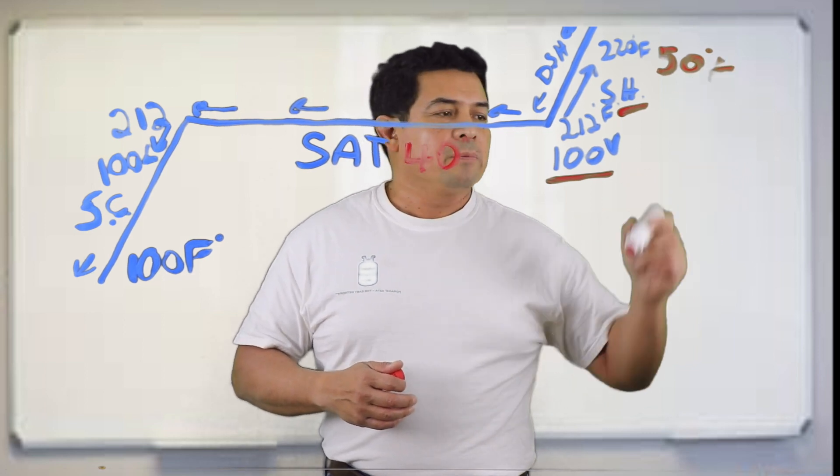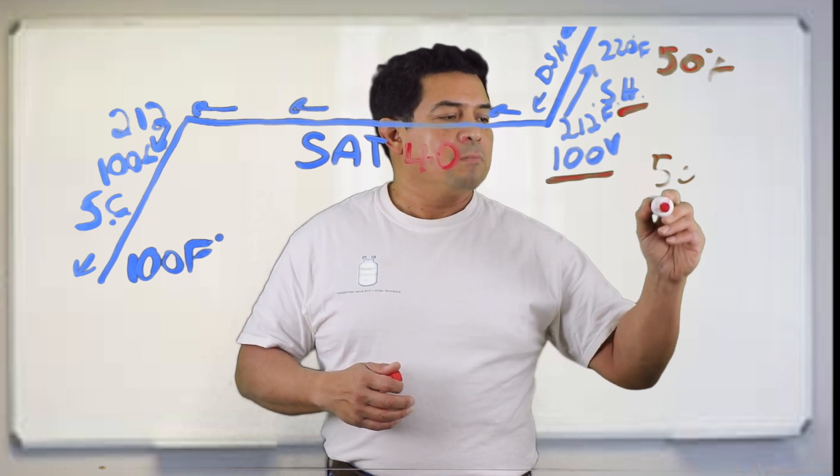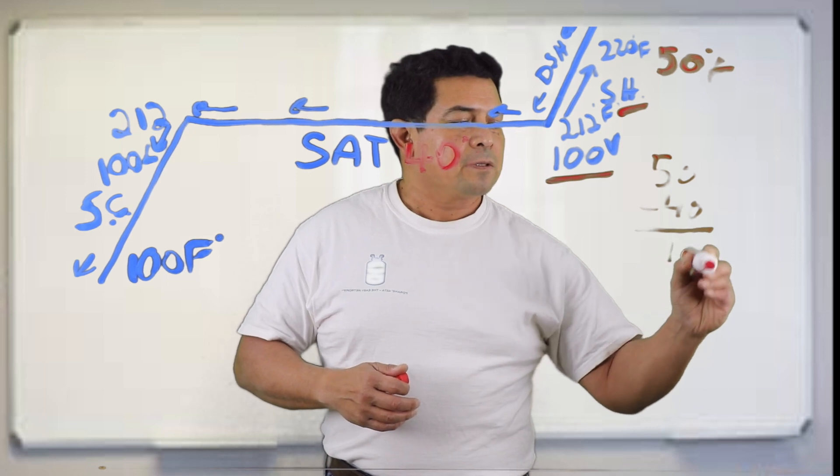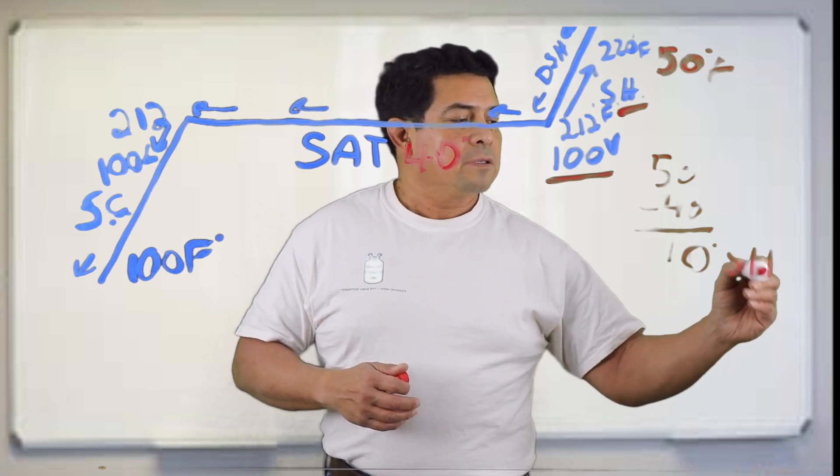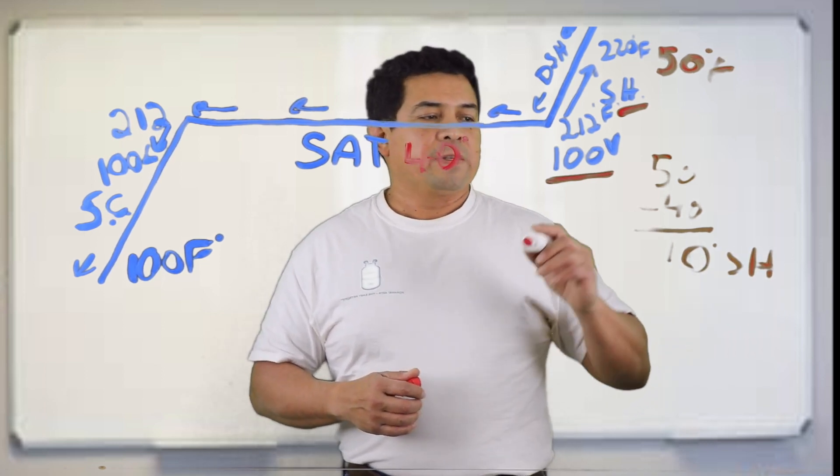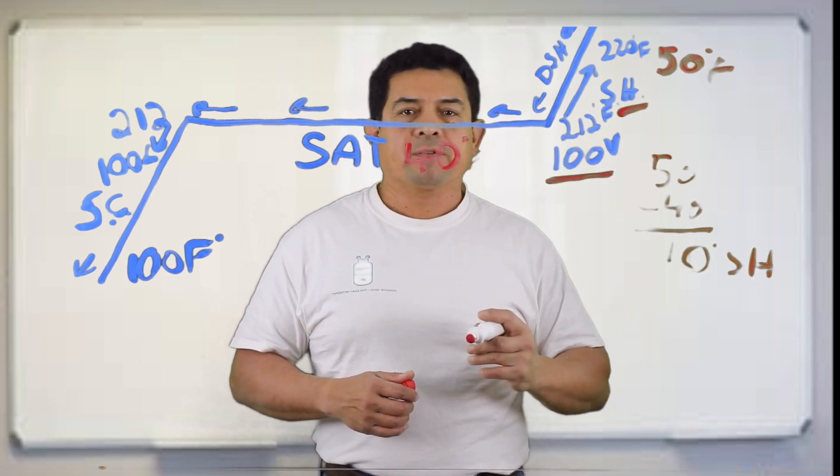So when we do the math, we can see that we have 50 minus the 40. That gives us 10, 10 degrees of superheat. This is where we come up with 10 degrees of superheat.